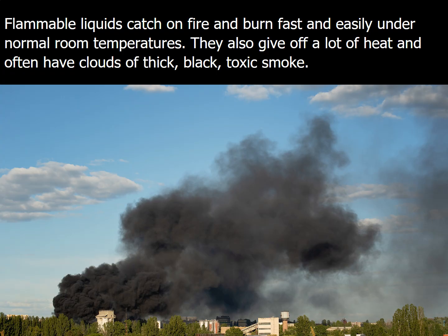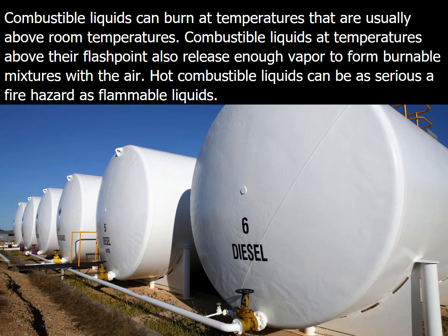Flammable liquids catch on fire and burn fast and easily under normal room temperatures. They also give off a lot of heat and often have clouds of thick, black, toxic smoke. Combustible liquids can burn at temperatures that are usually above room temperatures. Combustible liquids at temperatures above their flash point also release enough vapor to form burnable mixtures with the air. Hot combustible liquids can be as serious a fire hazard as flammable liquids.